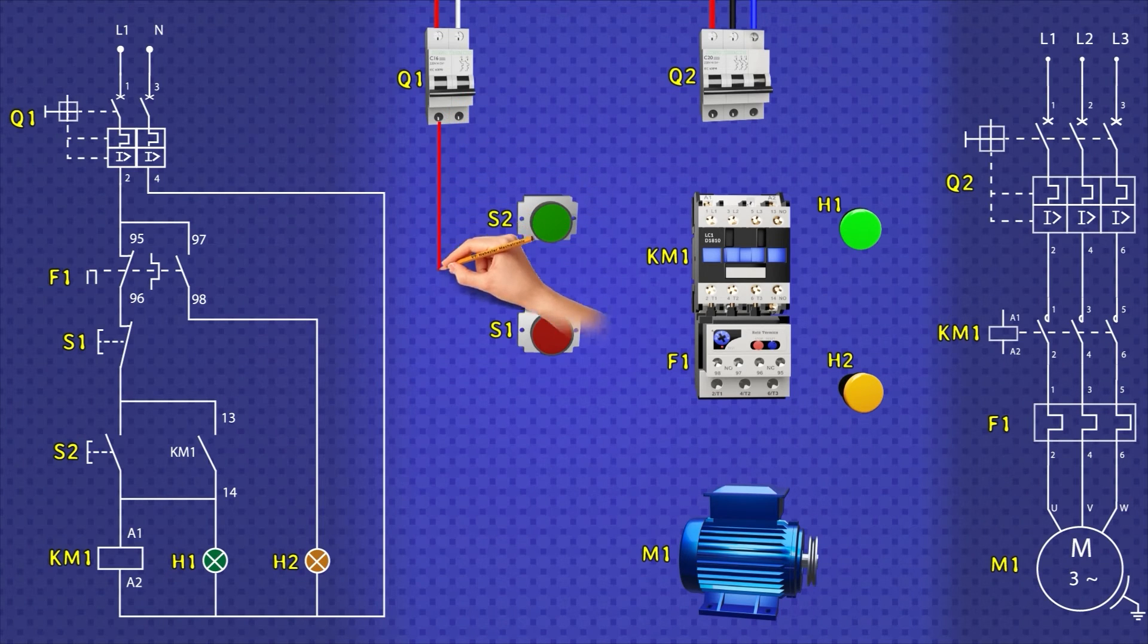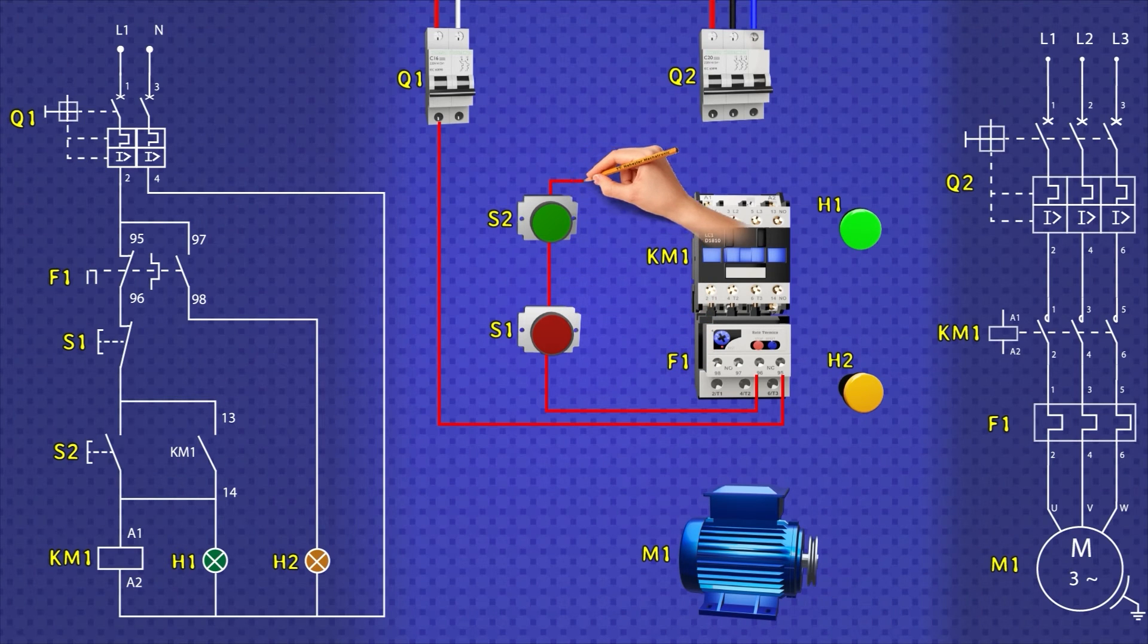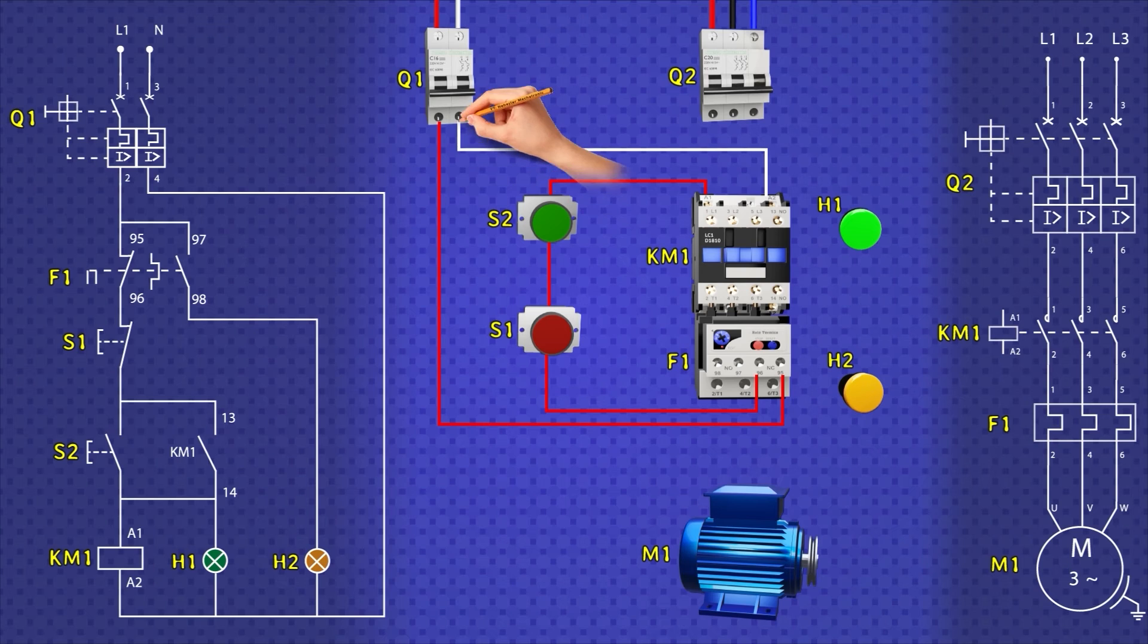I am going to hide the lines of force for a moment to focus on the command part. From switch Q1, it will be connected to terminal 95 of the thermal relay. From its output, which is terminal 96, it is taken and connected to the stop button S1. Now to the start button S2. From the output of this button, it is carried and connected to terminal A1 of the contactor coil. And from terminal A2, it comes out and is brought back to the two-pole thermomagnetic switch. Note that the red cable indicates phase or line 1 and the white cable is for the neutral. We continue. We connect from between the buttons and take it to terminal 13 of the contactor. From terminal 14, we carry and connect to terminal A1.